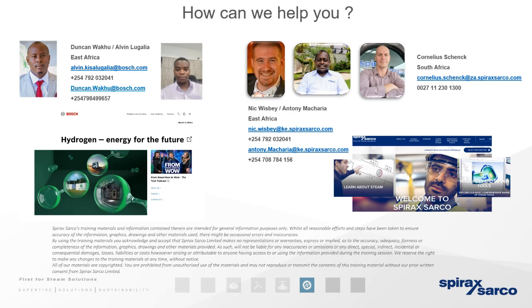Antti, do you remember how much we say you can save by recovering the heat from a blowdown vessel? 6%, I think, on fuel. But it also depends just how much blowdown you're doing. Alvin, does Bosch have an official percentage figure for heat recovery from blowdown? Heat recovery from blowdown is around 6 to 7% on fuel. And yes, you're correct. Remember, the blowdown module is not only used during blowdown, but also during normal operation in the desalting process.